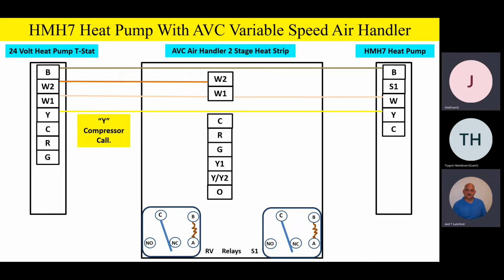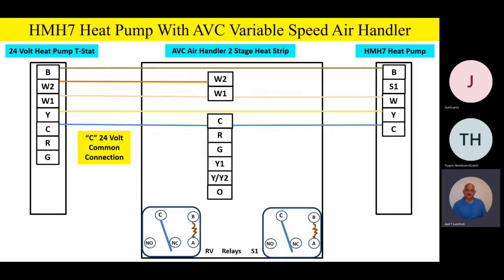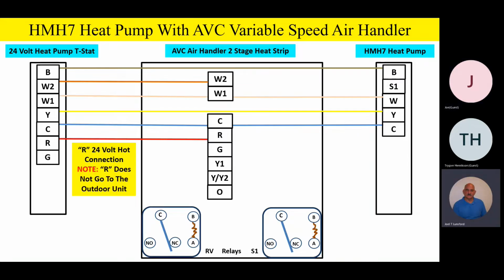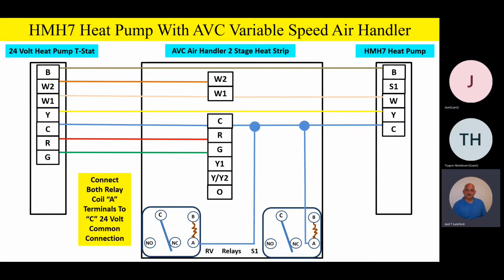Y terminal will go outside just like we had before. C is our 24-volt common. And again, this is all looking very familiar to everyone, I'm sure by now, because it's essentially the same wiring that we've had before. It's just that we're featuring two relays on a variable speed product. R terminal is 24-volt hot, and please remember, it's just going from the thermostat to the indoor product. And G is our 24-volt fan call. Now, where it starts getting a little bit different on the variable speed air handler and the variable speed furnace is we have a couple terminals on there that are going to be a little bit different. The O terminal has to be dealt with on a variable speed product, and we'll talk about that in a minute or two. Let's start out with our two relays.